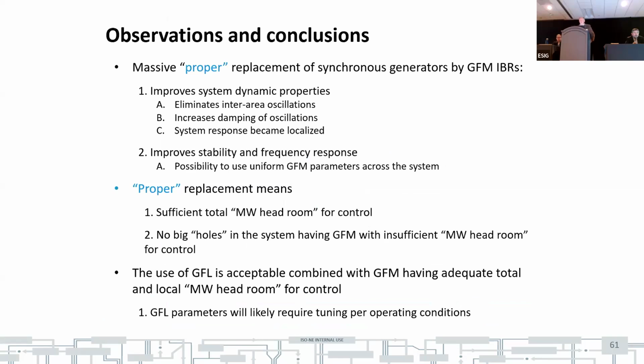So in general, the observations are the following. If you massively replace traditional generators by grid forming inverters in a proper way, results are very optimistic, at least based on this study. And what does it mean? You drastically improve dynamic properties of the system and improve stability and frequency response. And specifically, what does it mean? Practically elimination of inter-area modes, drastic improvement of damping of oscillation, and the system response becomes localized.